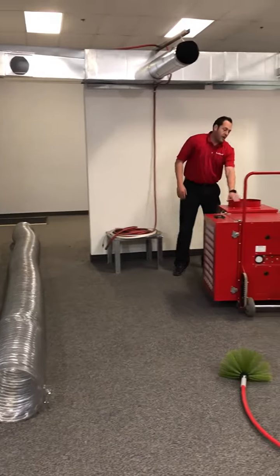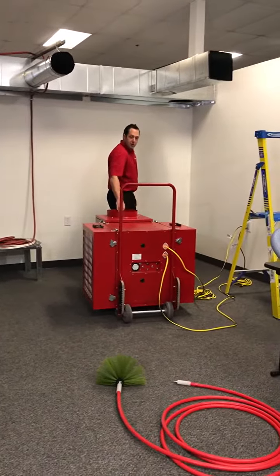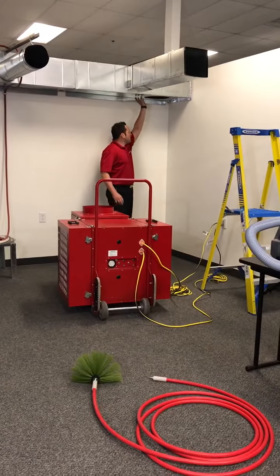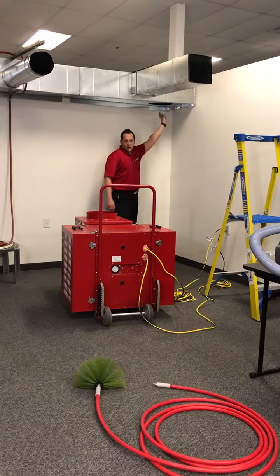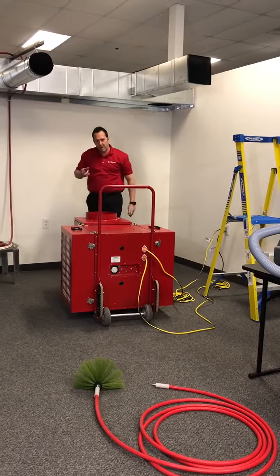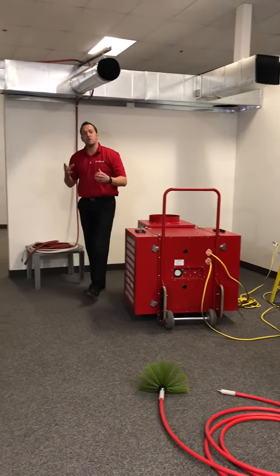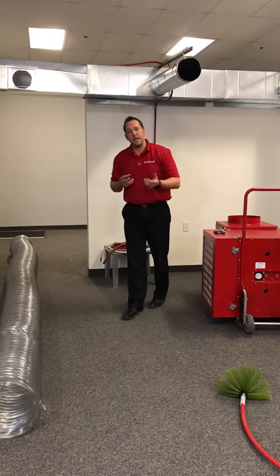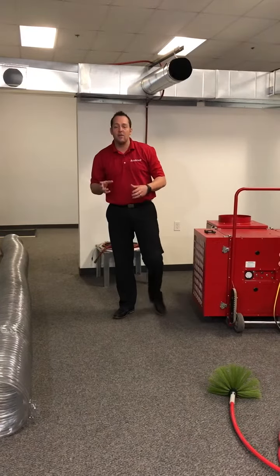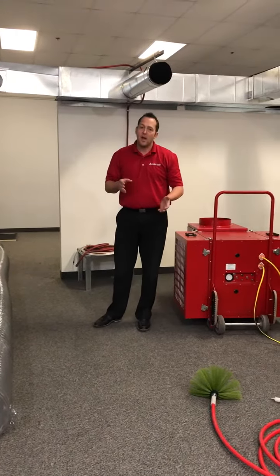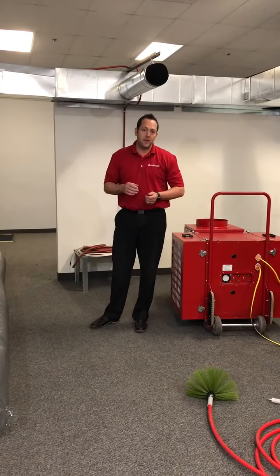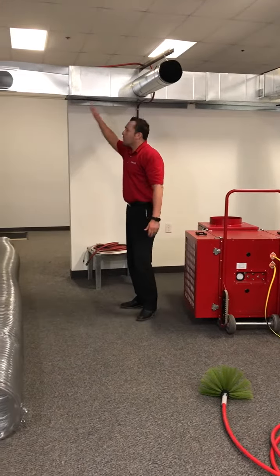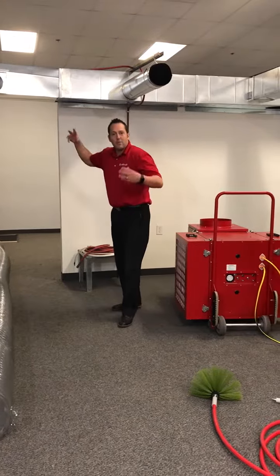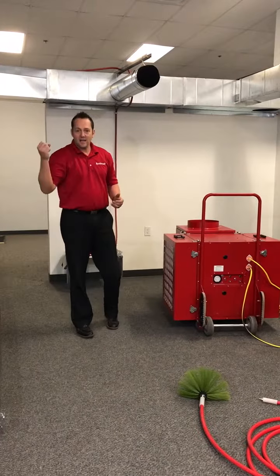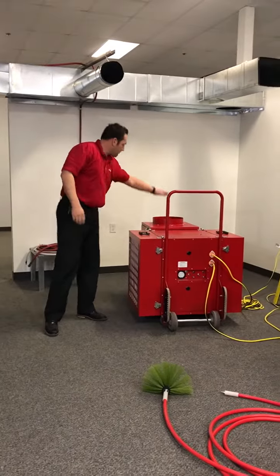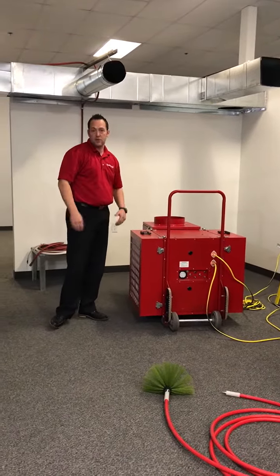You'll hook the connector hose to the machine itself, which we'll show you in a moment, and then hook the connector plate to the actual ductwork, using it to just create a vacuum. At that point, you can take the hose, with the brush connected to it, depending on the actual duct size, which will dictate the size of the brush itself. But starting from the furthest register from the air handler, you'll start working your way through the ductwork. Anything that the Rotobrush does not vacuum up will be pulled back into the actual collector, into the reservoir.